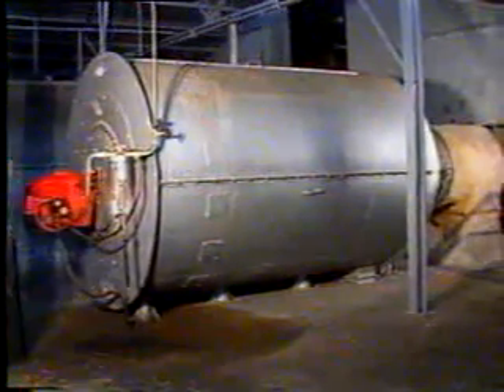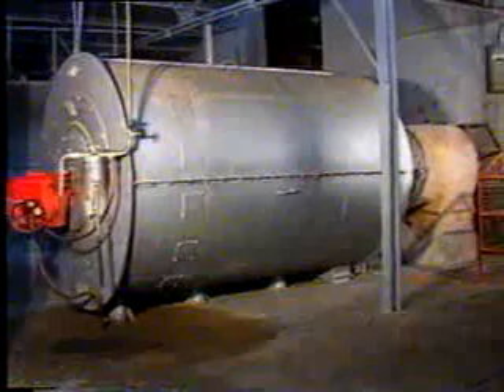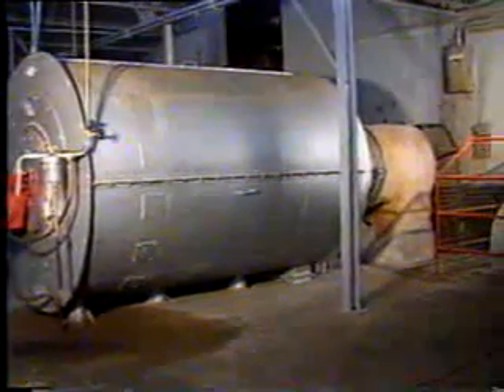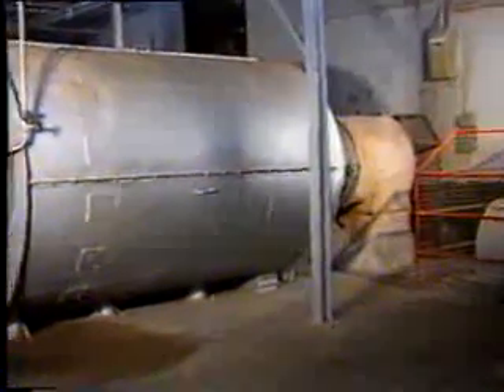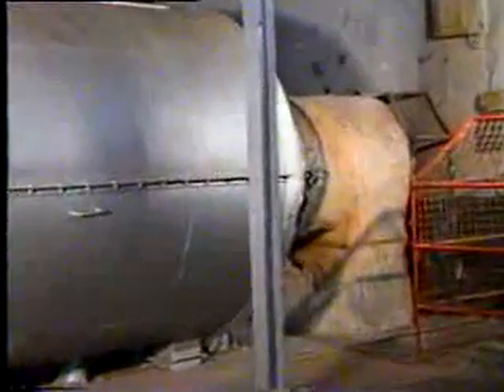Now let us look at two air heaters which are commonly used along with fluid bed dryers. This is an oil-fired heat exchanger. The volume of air sucked through the heat exchanger can be adjusted by the operator to get the optimum requirement of the dryer. The fan delivers hot air to an underground duct which is connected to the dryer.